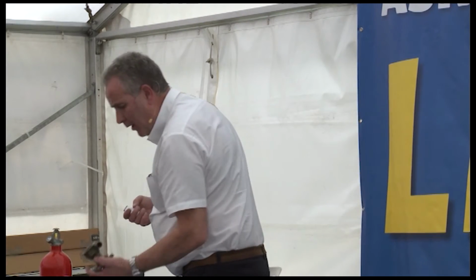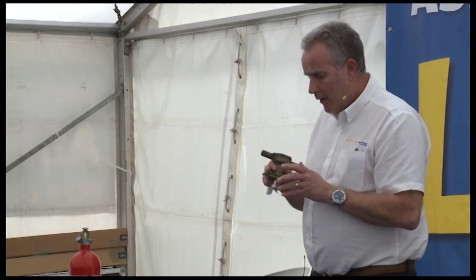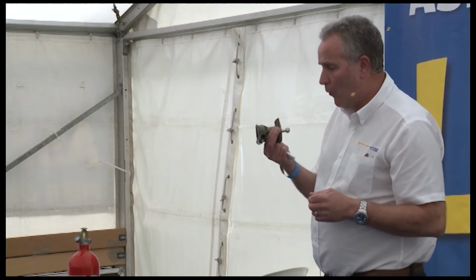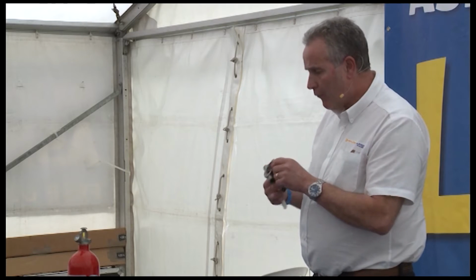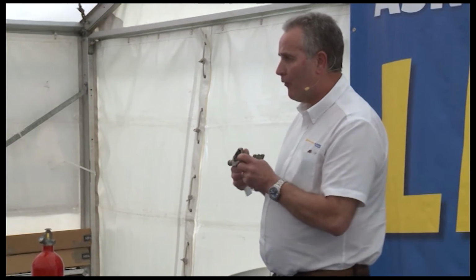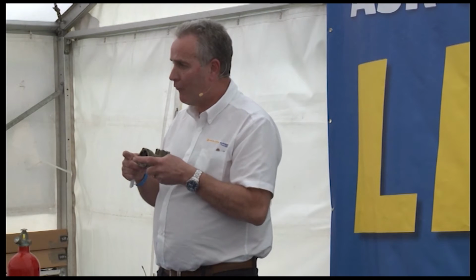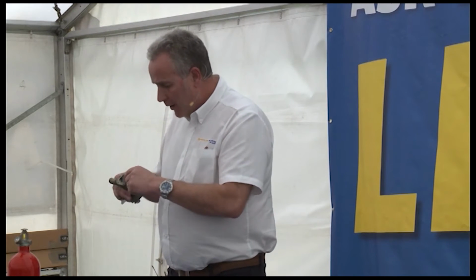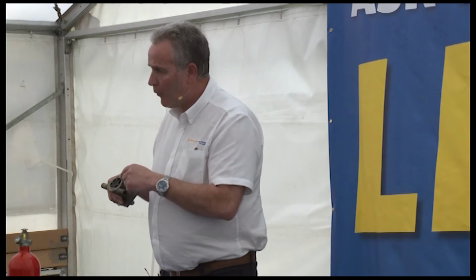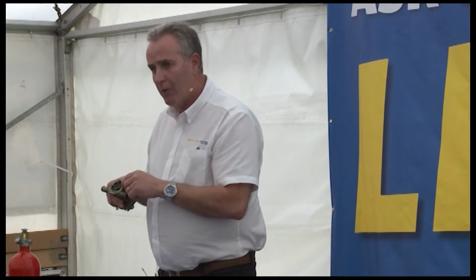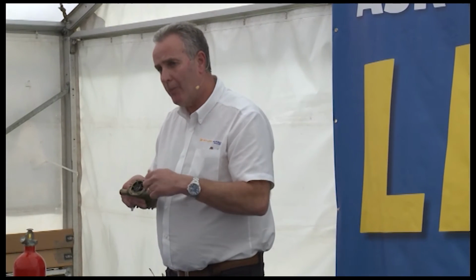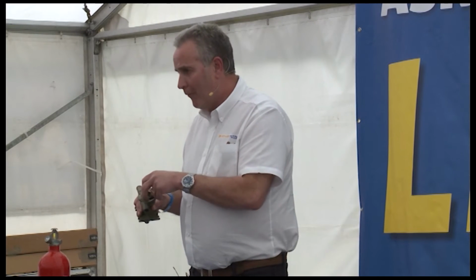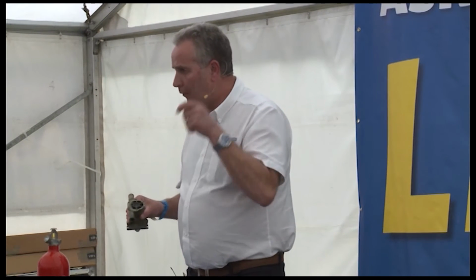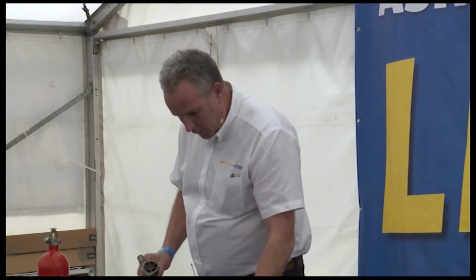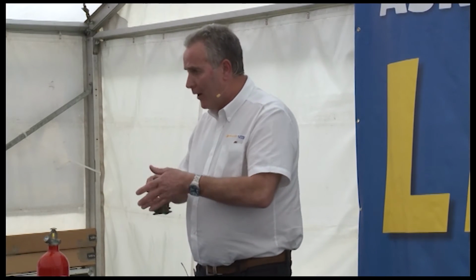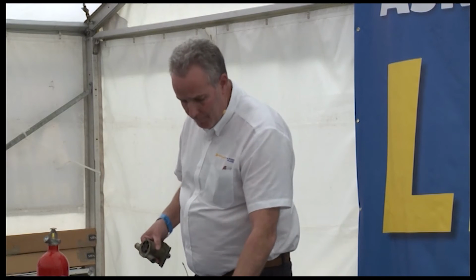If you're changing the impeller, now this is obviously a nice small one, so it's quite easy to do, but be careful when you take the impeller out that you don't use, like some people do, 2 levers either side to try and pry it out, because the side walls are very thin, and you can damage where the screws go on the cover plates. So if you've got a little pair of pliers or something along those lines, that will pull it out, and then try to get them back in. The small ones are quite easy, just do a little rotation and they pop in.